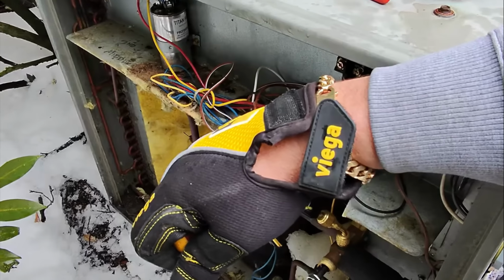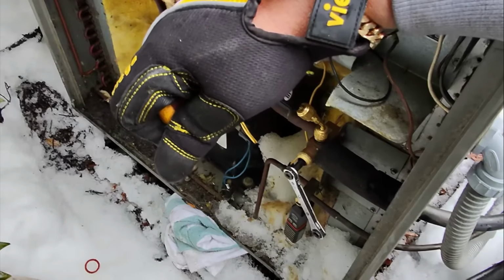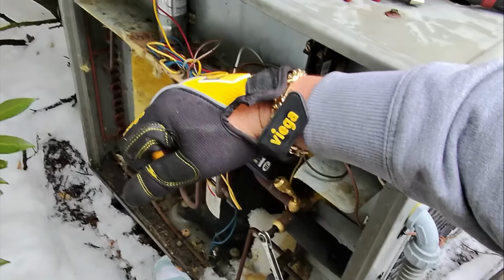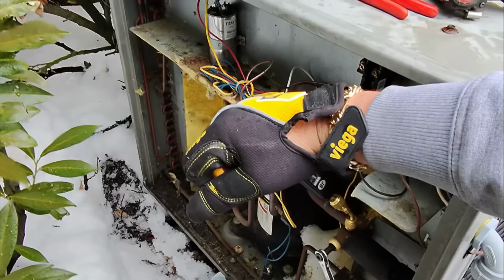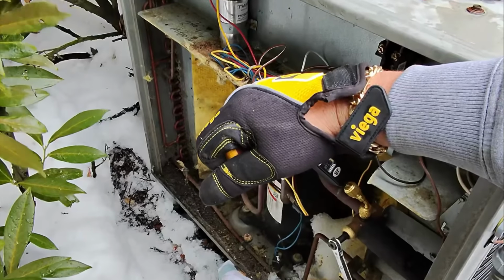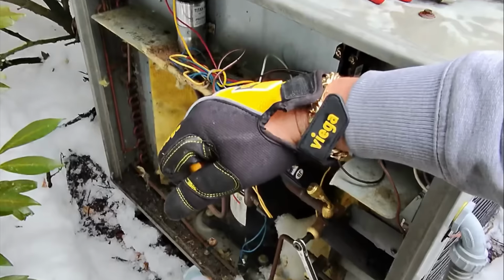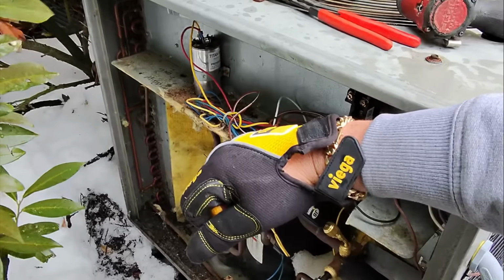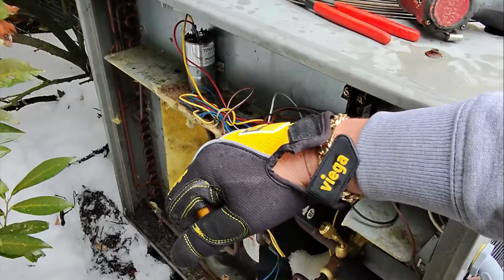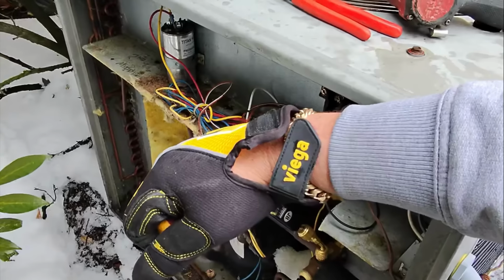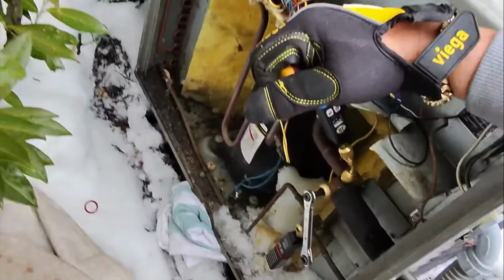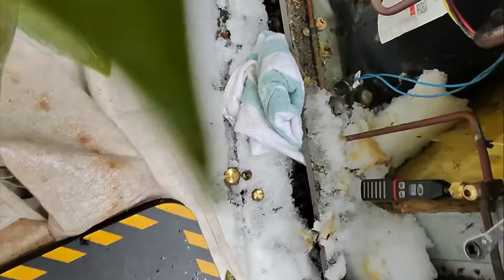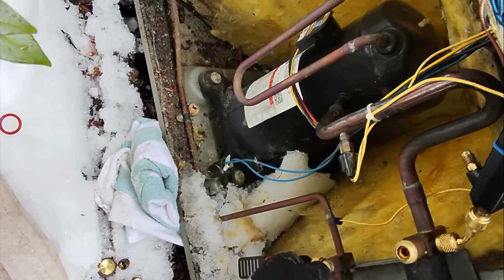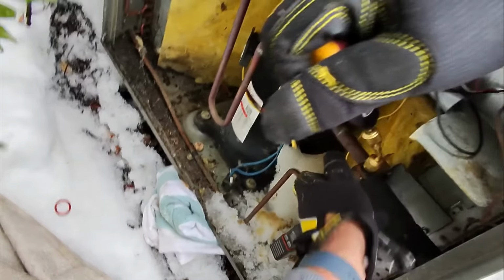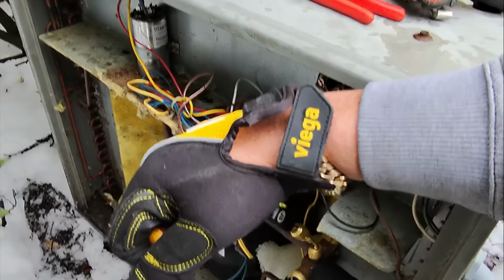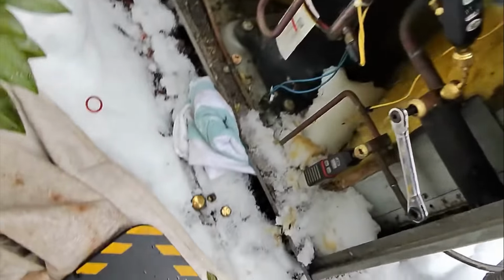Right now we're at 15 psi, 13, 12, 9, 8. Sometimes it takes a couple moments, and sometimes your compressor will go out and bypass, and it won't let you pump down. We're at 4.2 psi, 3.6. Going back up again, 4.5. All right, going back down. Make sure these valves are fully closed. Excellent. 2.6, 2.4, 2.3, 1.9. We're slowly dropping.